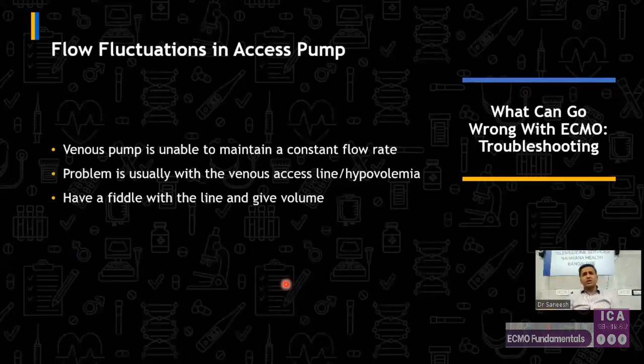What are the flow fluctuations in the access pump? Why do they happen and what is it? Venous pump is unable to maintain a constant flow rate, that is called flow fluctuation. And why does it happen? Most of the time it is due to hypovolemia, or there might be a circuit thrombosis. So fiddle around the line, find out the reason and correct the reason.